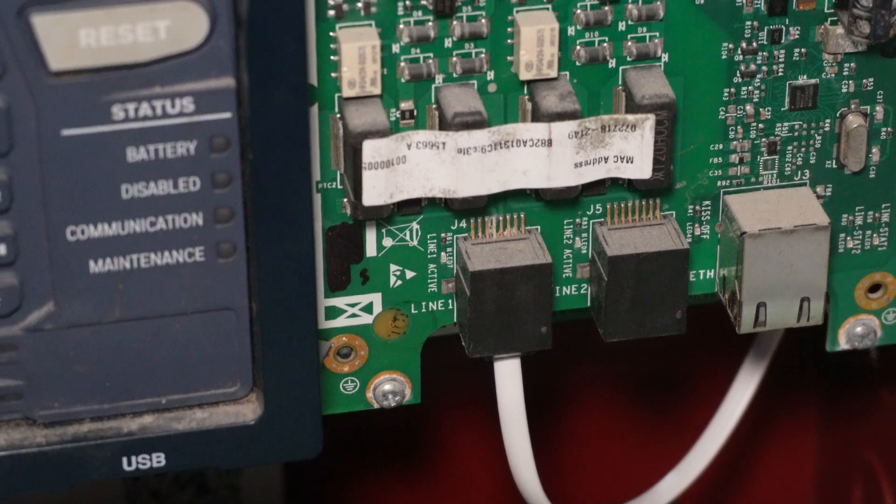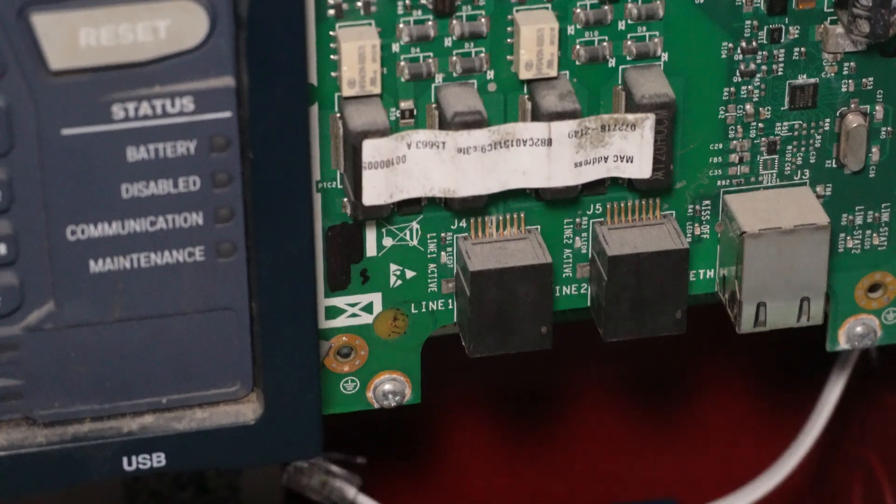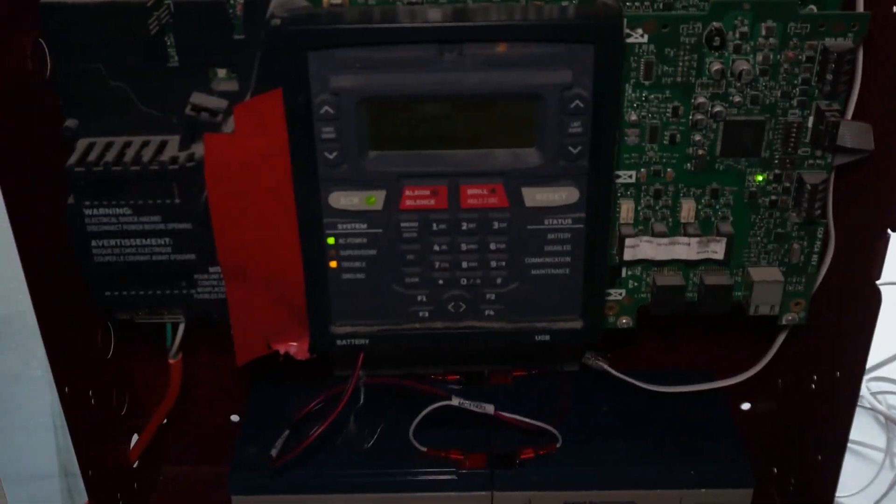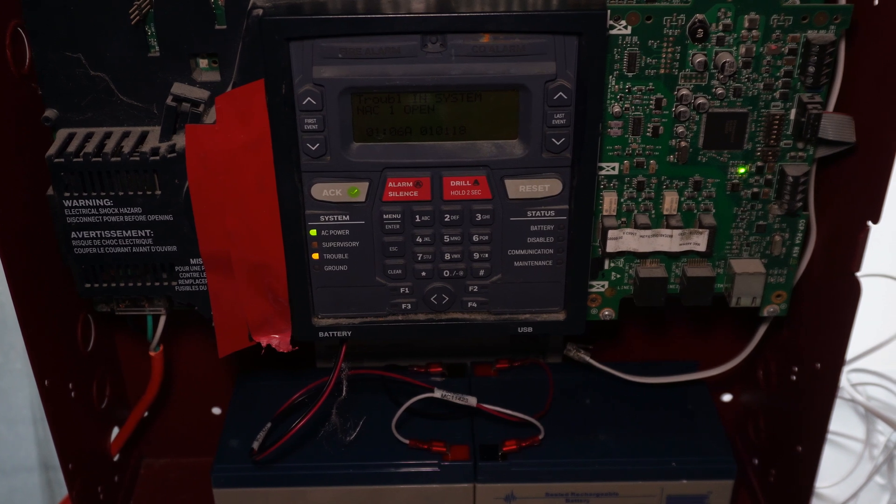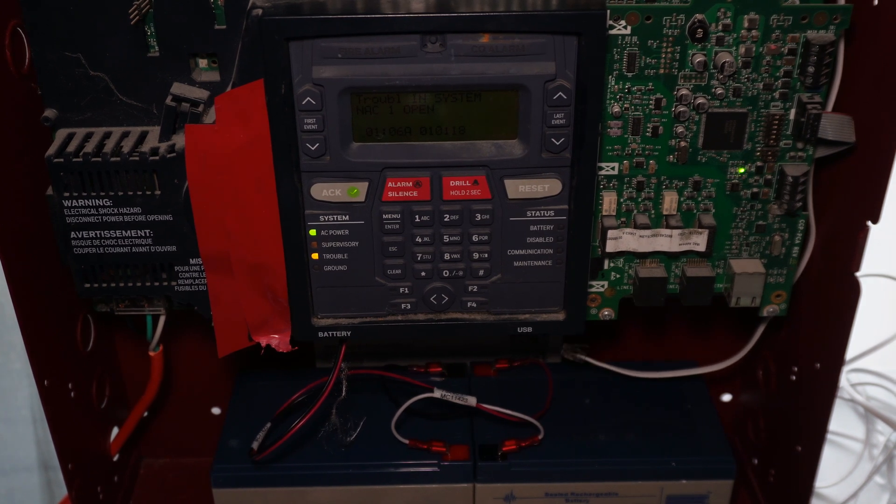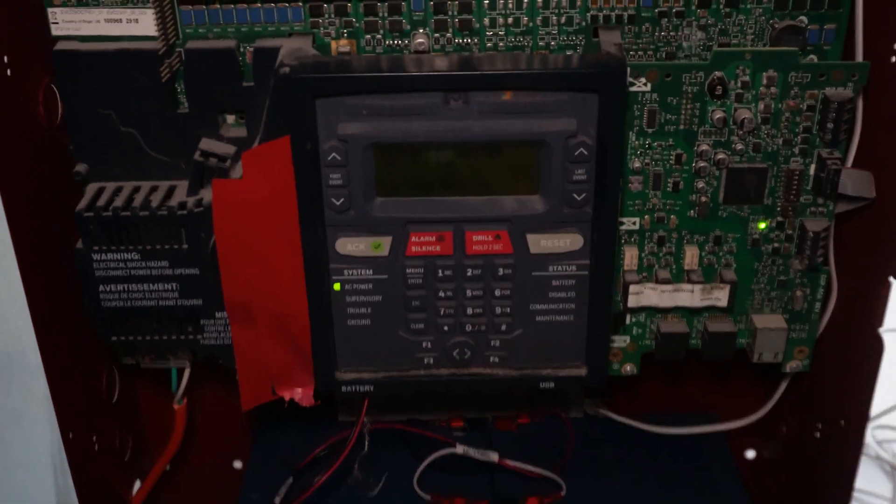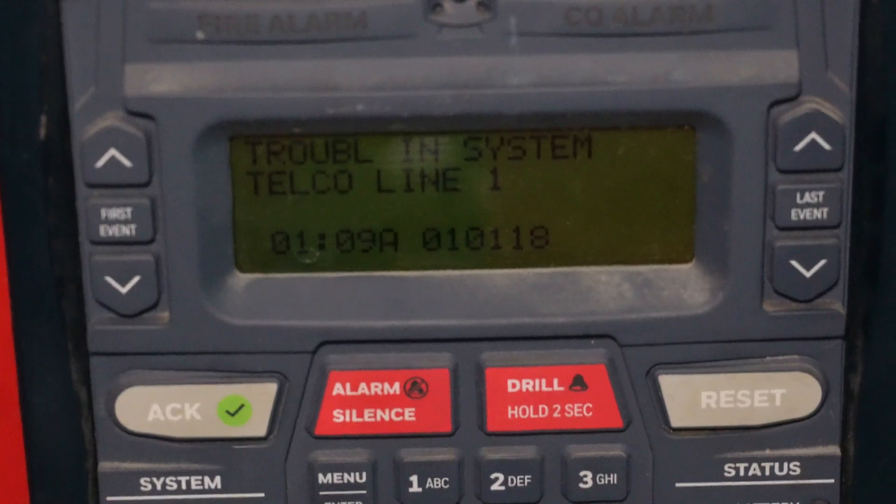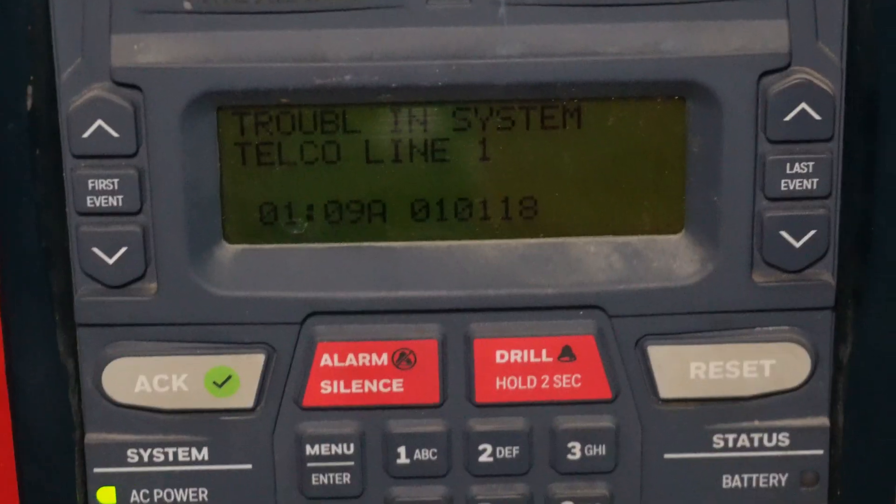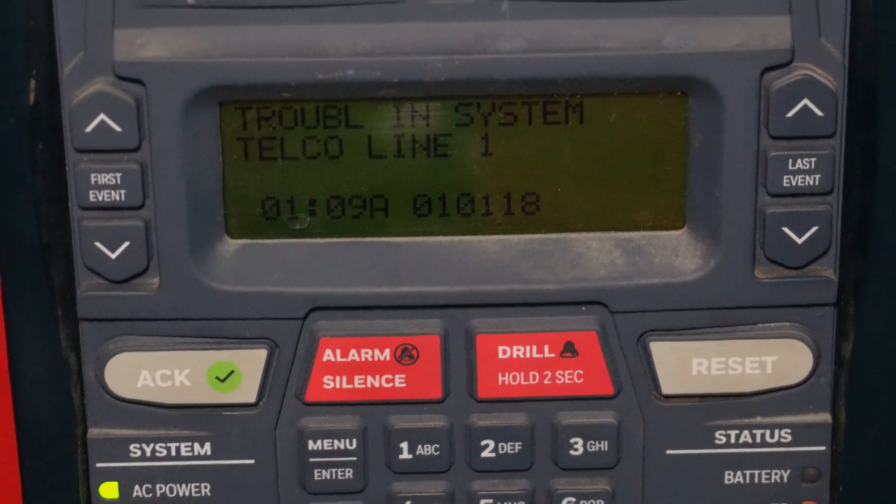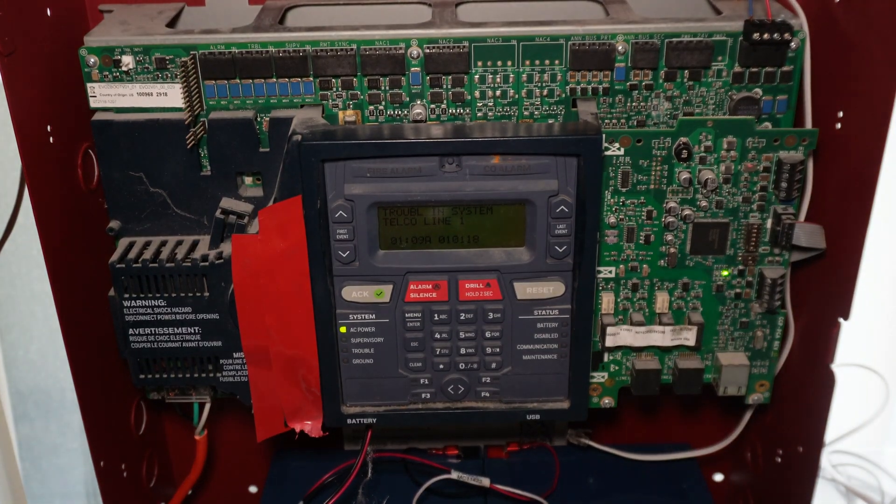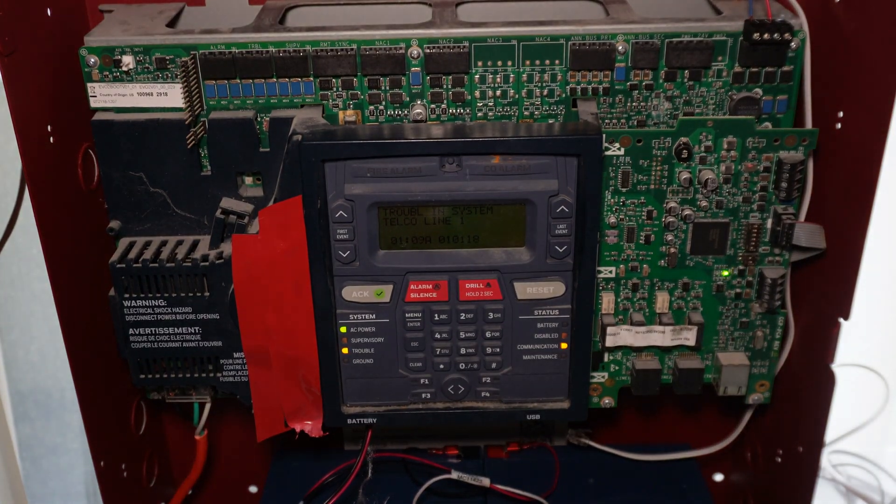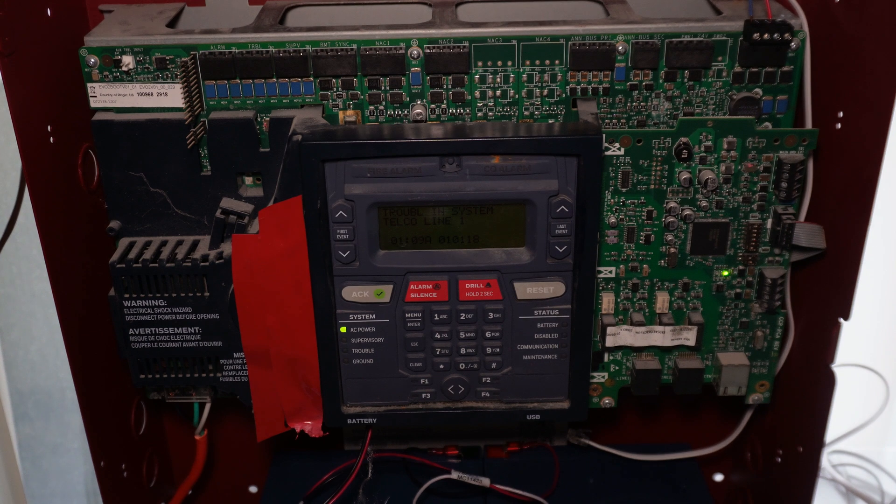And now I'm actually going to disconnect this. And now after it tests it a few times and realizes that there's no voltage there, the system's going to go into trouble. Oh yep, there it goes. It's in trouble now. Yep, for telco line one, since we pulled the plug, it thinks the line's cut now. So I think that's going to do it for this episode. Thank you guys for watching.